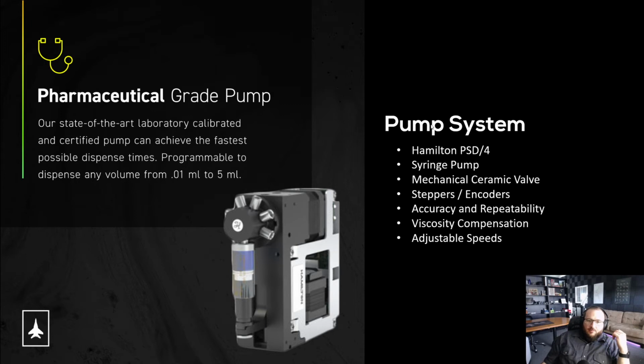Moving on to the pump, we integrate a Hamilton PSD4, which is a pharmaceutical grade syringe pump. The valving system is ceramic on ceramic, so there are no one-way valves, there's no pressure actuation in here. There's an actual motor sitting right here which turns a ceramic piston inside to select the correct port.